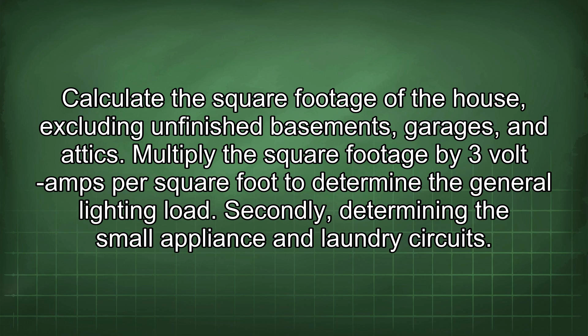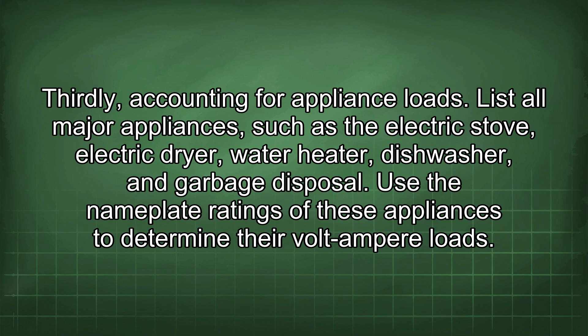Secondly, determining the small appliance and laundry circuits. The NEC requires at least two 20-amp small appliance circuits for the kitchen and one 20-amp laundry circuit. Each of these circuits is calculated at 1500 volt-amps. Therefore, the total load for small appliance and laundry circuits is 3 times 1500 volt-amps, which equals 4500 volt-amps. Thirdly, accounting for appliance loads. List all major appliances, such as the electric stove, electric dryer, water heater, dishwasher, and garbage disposal. Use the nameplate ratings of these appliances to determine their volt-ampere loads.